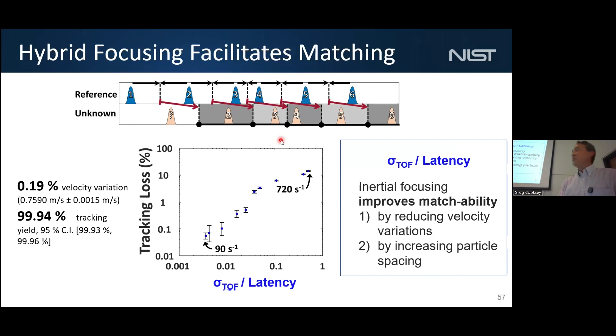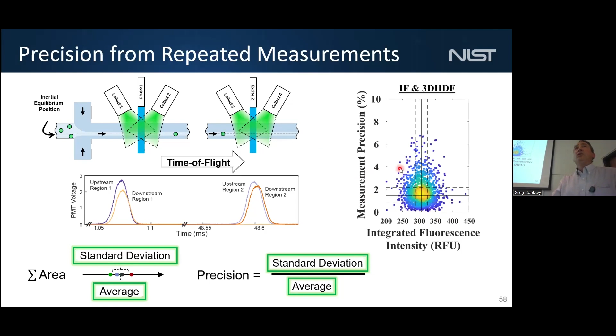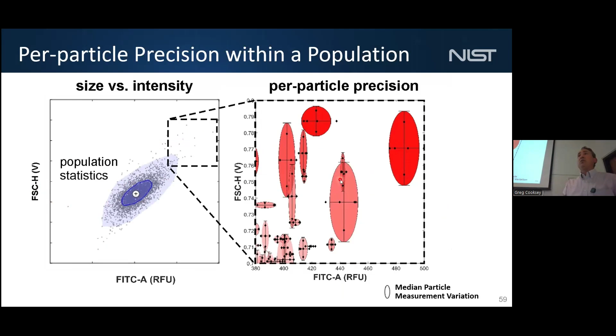So now that we can match measurements, we can normalize them and calculate a coefficient of variation to give us an estimate of the precision of that particle's measurement. So now we can plot, for each particle's intensity, how well we knew that particle's intensity. Going back to a traditional scatter plot for cytometry, not only can we see the intensities of the distributions that we measure, but we can actually put a boundary around how well we know each particle's intensity distribution. And we can modify the control of the instrument to understand how well it's replicating the measurements.